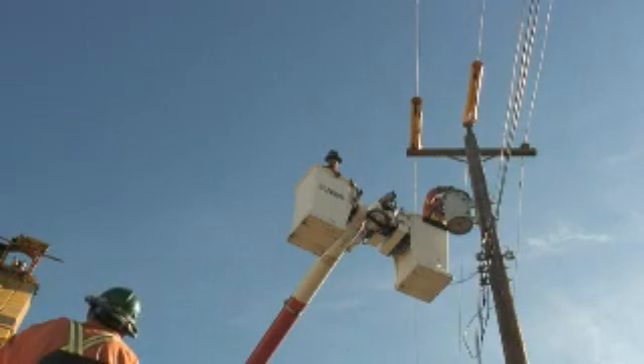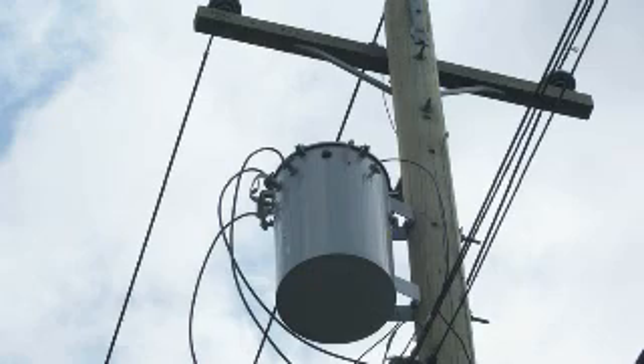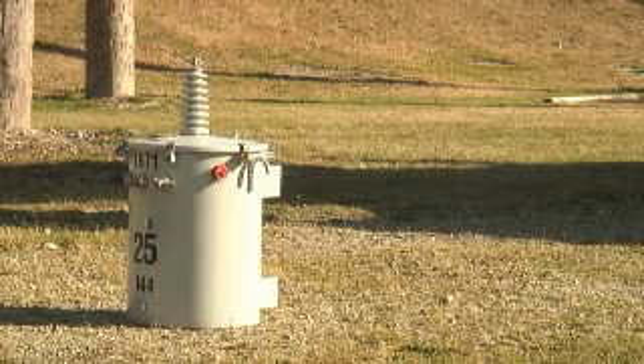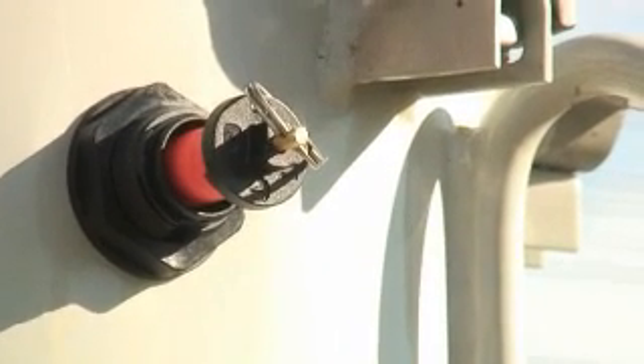Unfortunately, these procedures are not always followed because of the urgency to restore power quickly. Industry studies conclude that 1 in 5 transformer re-energization operations involves a transformer with an internal fault. To identify faulted transformers and enhance line worker safety, IFD Corporation developed the Internal Fault Detector, or IFD.